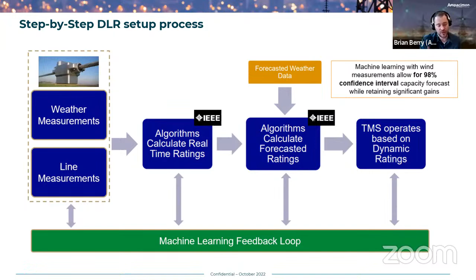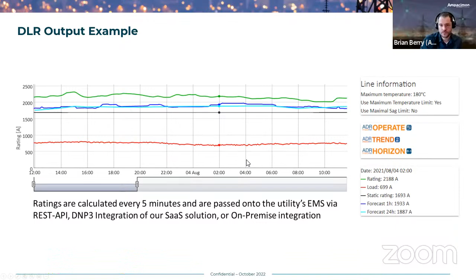Over here you're looking at an example - this is a picture of our HMI showing a static line rating, forecasted line rating 24 hours ahead, 1 hour ahead in blue, and then the actual dynamic line rating in green, as well as the load. That's what it looks like in our system.